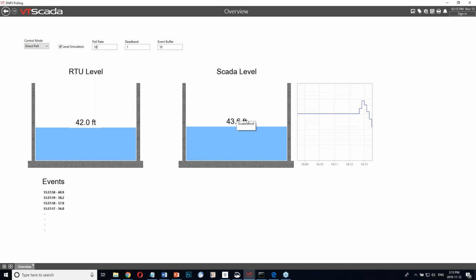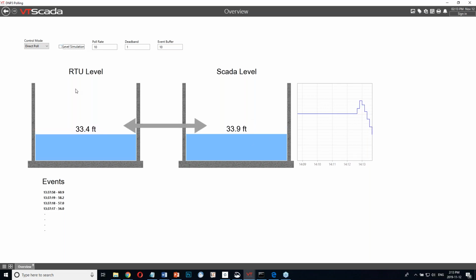And we're sampling it based on time, and a Modbus protocol or DNP3 with direct polls really can only do that by time, which may not be most useful. And the other thing that happens is if the level stops moving, or if you're monitoring something like a reservoir level or a lake river level, something like that, that may not change very often. A significant change may only occur once an hour or a couple times a day, who knows. You're going to be polling still every 10 seconds just to discover that it hasn't changed.